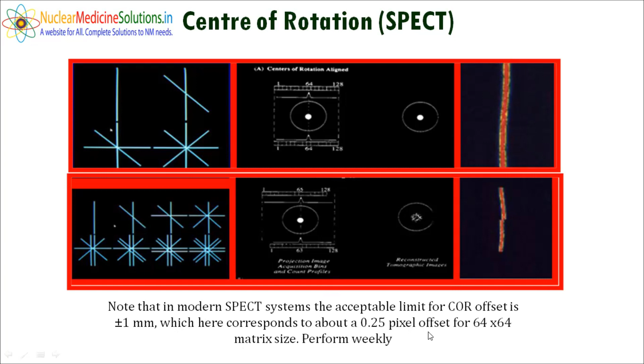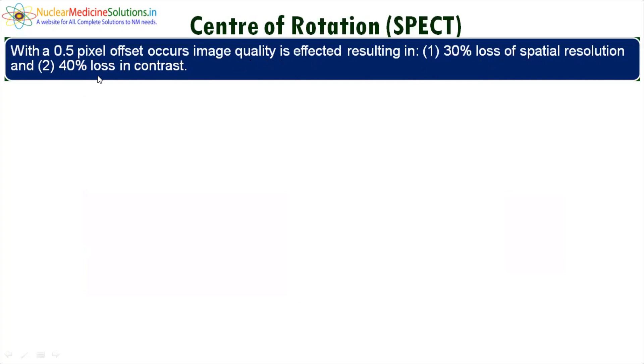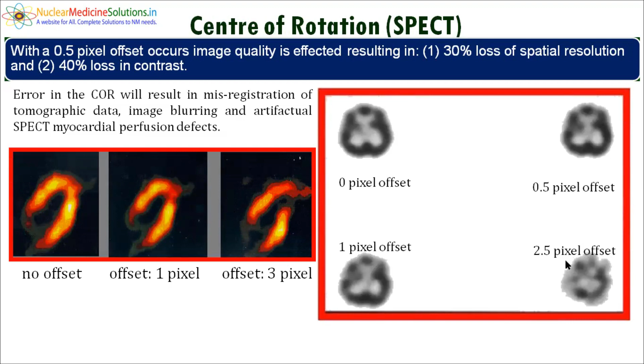If a 0.5 pixel offset occurs, the image quality is affected, resulting in 30% loss of spatial resolution and 40% loss in contrast. By seeing this example, you will understand more about the COR and how it affects your image quality. You can see here, when there is a 3 pixel offset, the resolution of the image becomes worse compared to when there is no offset in the COR. This is the second example. When there is a 2.5 pixel offset, the resolution of the brain image becomes worse compared to 0 pixel offset.